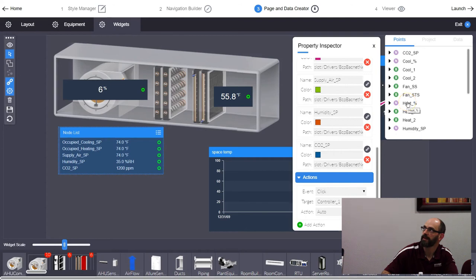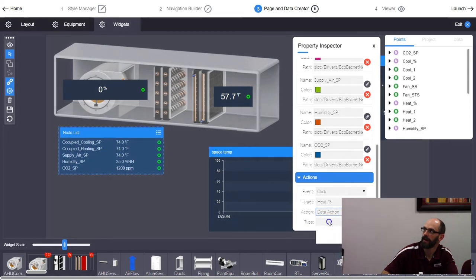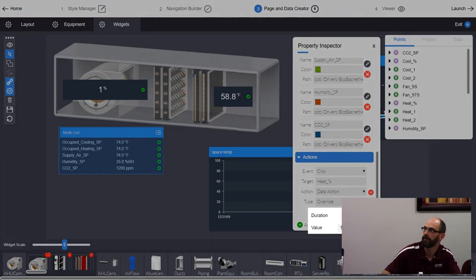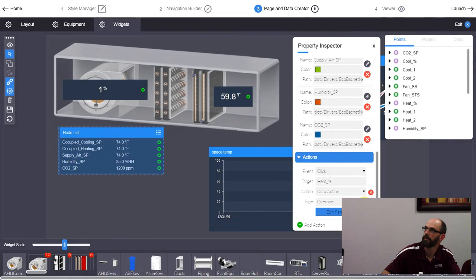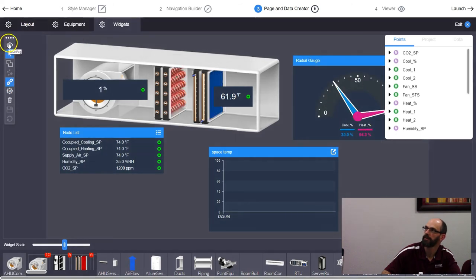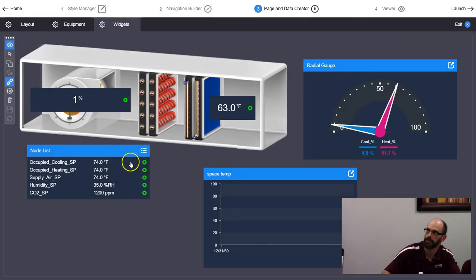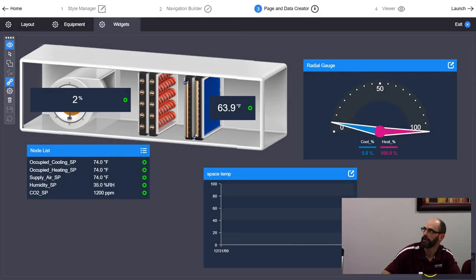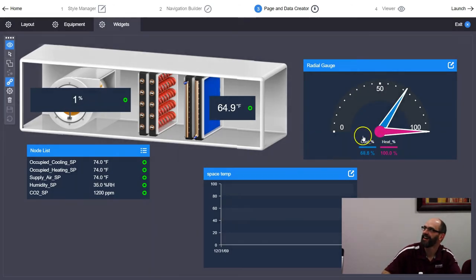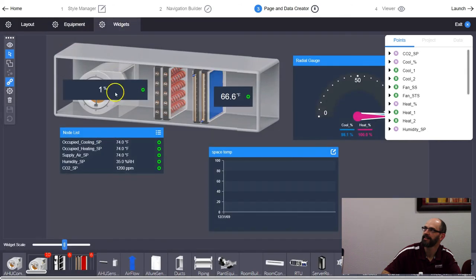For example, I can take heat percent and add a data action: override it permanently to 100%. When I click on the node list, my little hand icon comes up, and the data action overrides heating to 100%. You can also add another action — double-click to release the override. So you'd add a second action on double-click that takes heat percent to data action and sets it to Auto. Save.